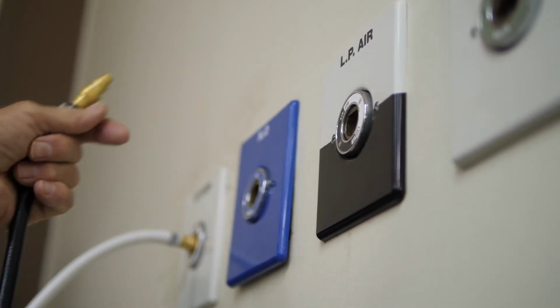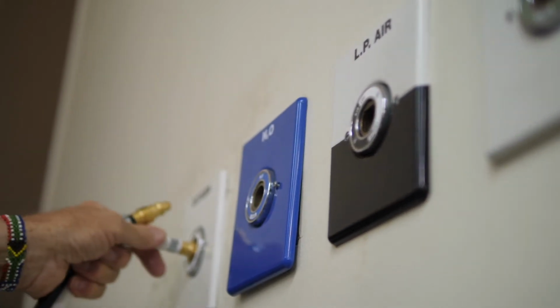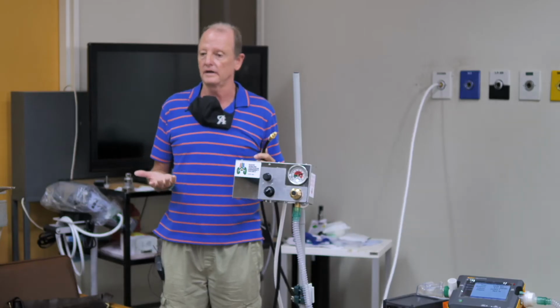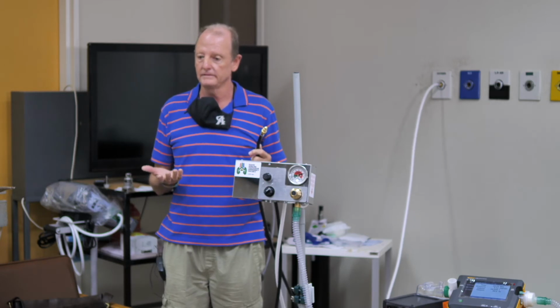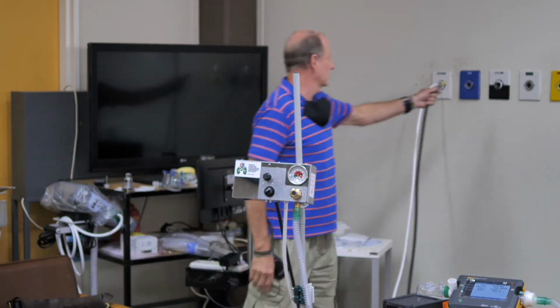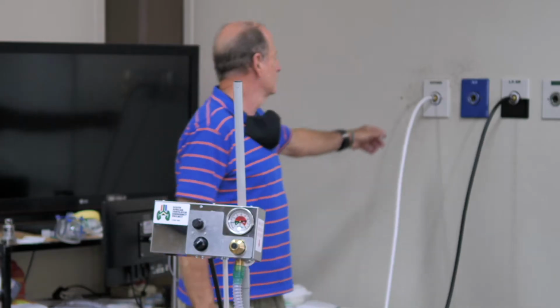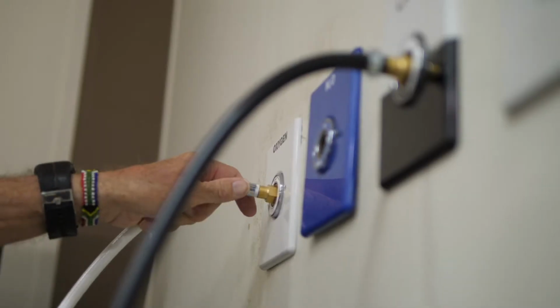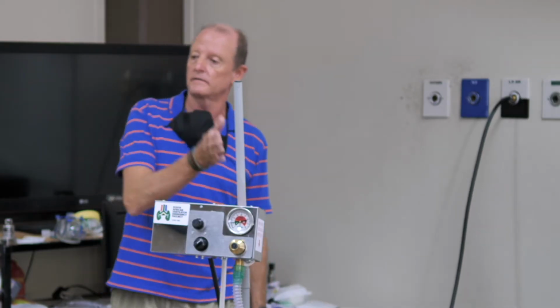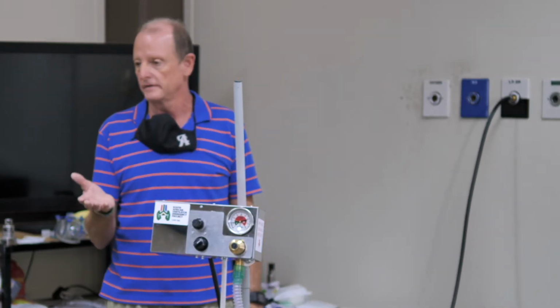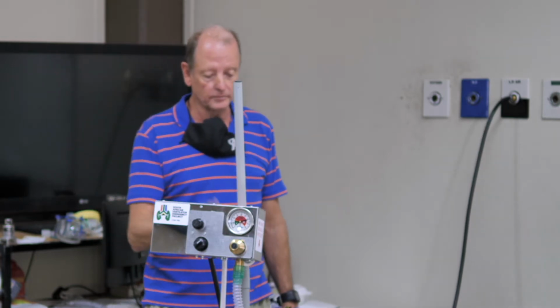Okay, you know what this means: either only one gas is connected. So you want to check now that it rectifies itself. Do the other gas, oxygen, pull it out. You must get an alarm as well. So we've checked the air, we've checked the oxygen. Okay? And it's as simple.